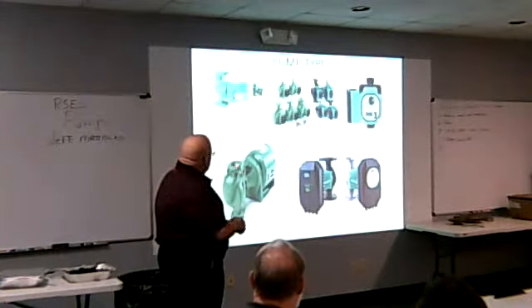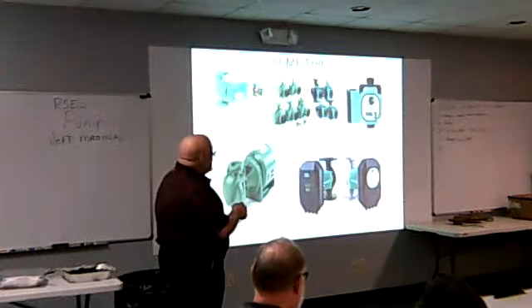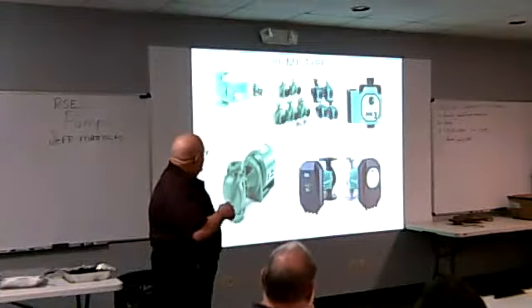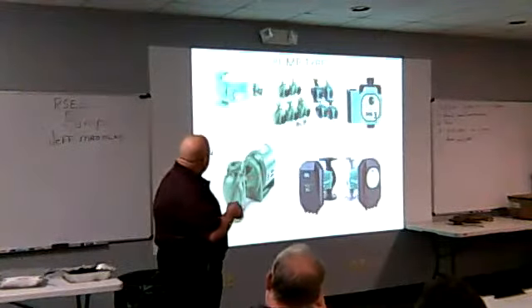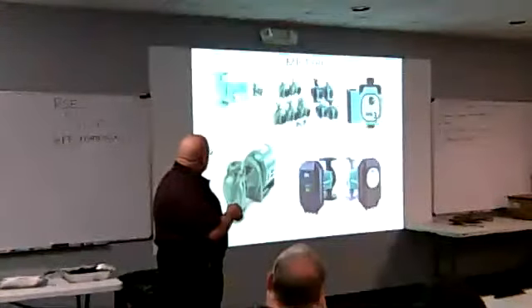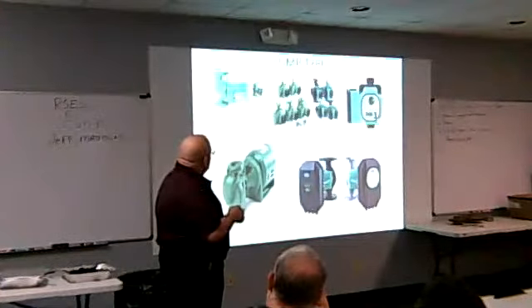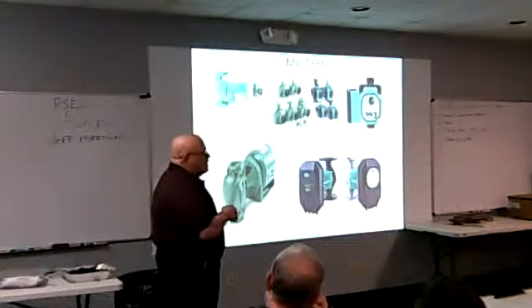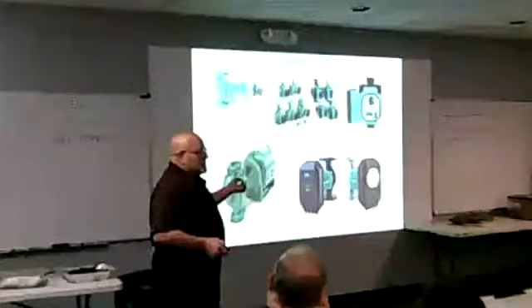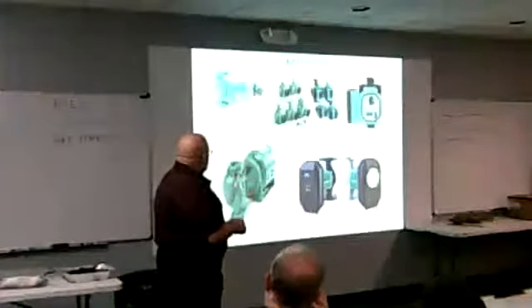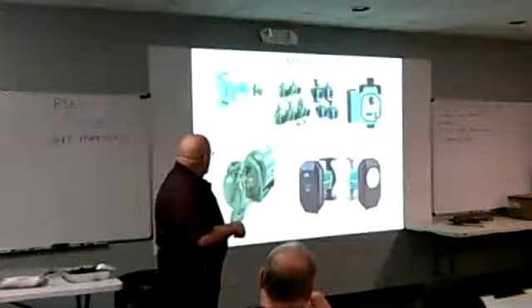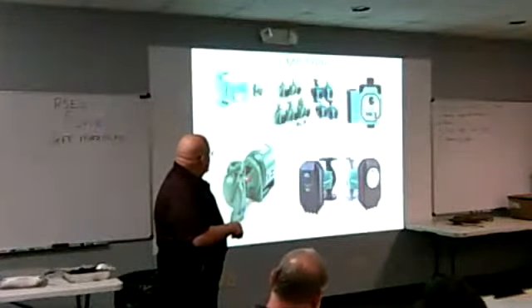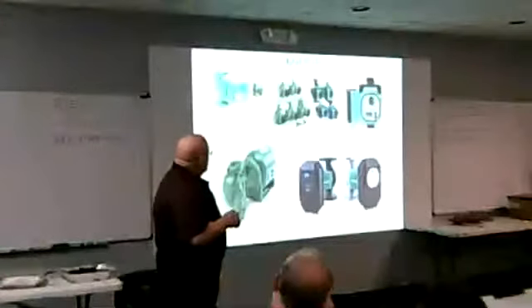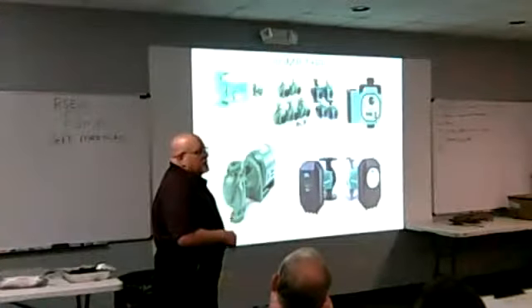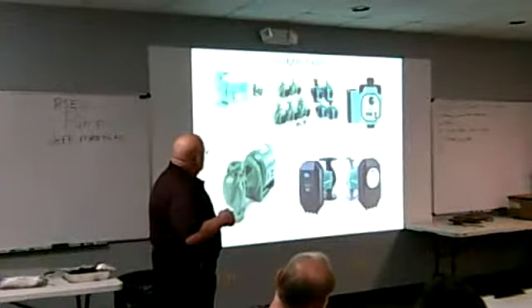These pumps basically do the same thing here. These have a little cartridge inside of them. So when you want to repair these, they have a mechanical seal. These have an O-ring. There's a little cartridge in here with the impeller built in. When you want to repair these, you pull out the 4 bolts, take off the motor, the cartridge goes in the garbage, and a new cartridge goes in. Much easier to put on. No mechanical seal to fail, no coupling. There's a spring coupling in these. So these are becoming much more prevalent, and over the years they're building more and more of those.